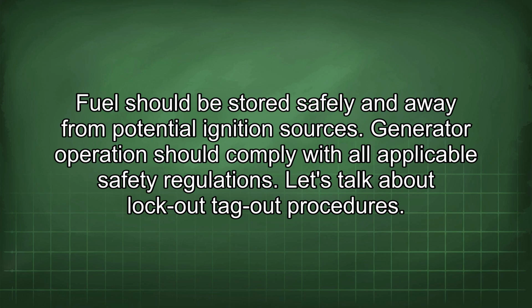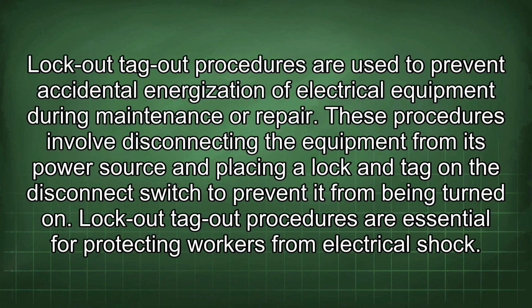Let's talk about lockout-tagout procedures. Lockout-tagout procedures are used to prevent accidental energization of electrical equipment during maintenance or repair. These procedures involve disconnecting the equipment from its power source and placing a lock and tag on the disconnect switch to prevent it from being turned on. Lockout-tagout procedures are essential for protecting workers from electrical shock.